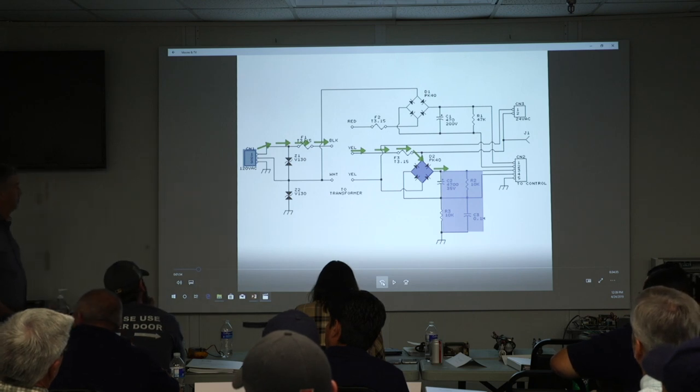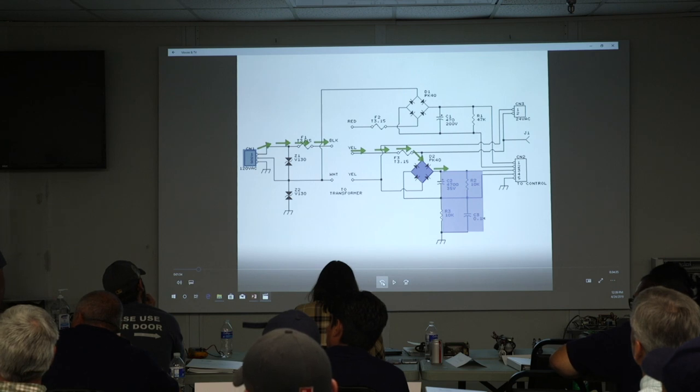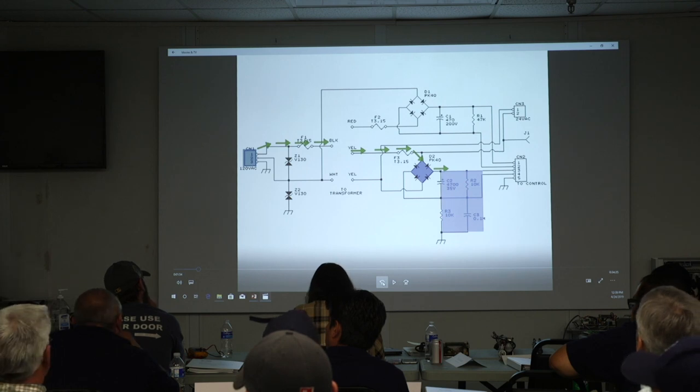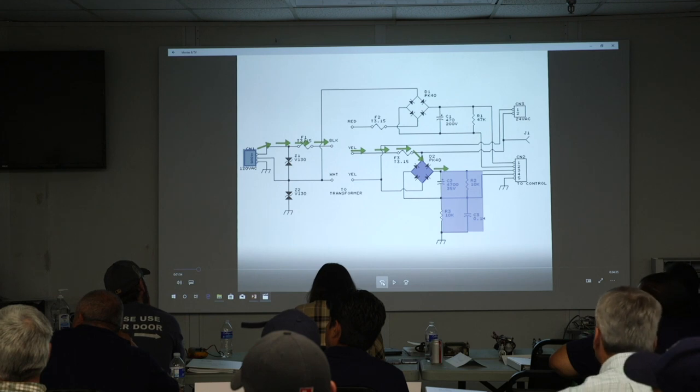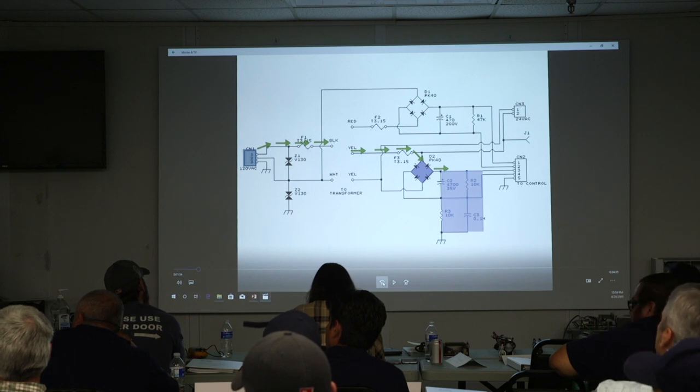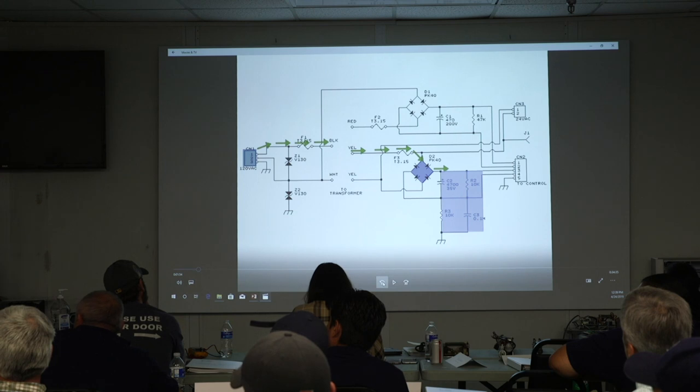The other thing, and this is kind of off topic, but when I have guys checking resistance, there's resistors right below that plug. One of them is a 10 ohm. I have them unplug the control and go to ohms and look at those resistors, and if they tell me it's 10, then I know that. There's a lot of guys who don't know how to use them either. So that's something I think is useful too.